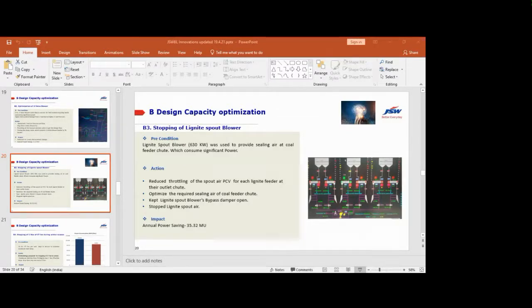So we reduced the throttling losses in these control valves and kept them fully open, optimized the air of the lignite feeder sealing air, and opened this bypass valve. By doing these 3 exercises, we were able to stop the lignite spout blower, which was consuming 630 kilowatt per hour. The impact is an annual power saving of 35.32 MU.